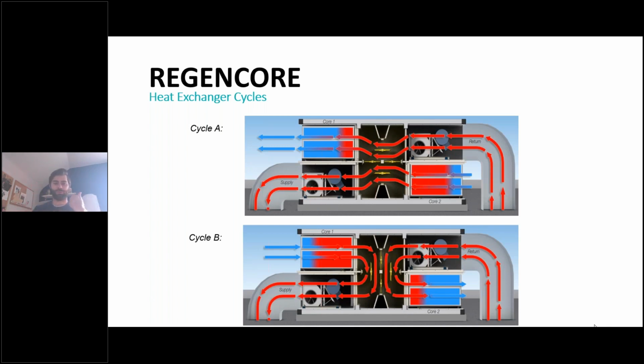So there's the main cores, which are pleated aluminum that is corrugated, so it's stacked on top of each other. They act as thermal batteries. All they are doing is capturing energy from your return air and then discharging that heat back into your supply air. Then you have 2 fans, and then you have the brains of the unit, which is really the damper section within the middle.